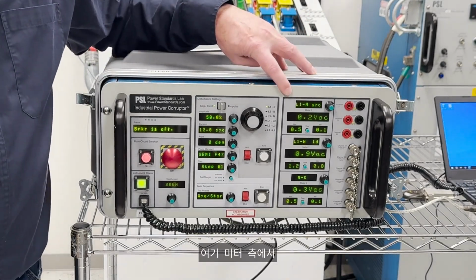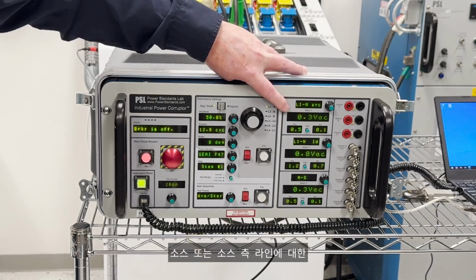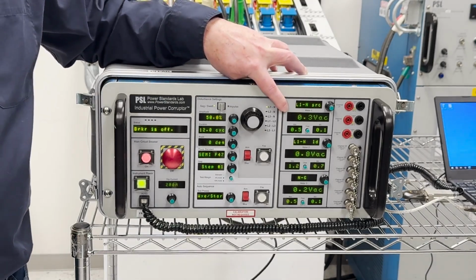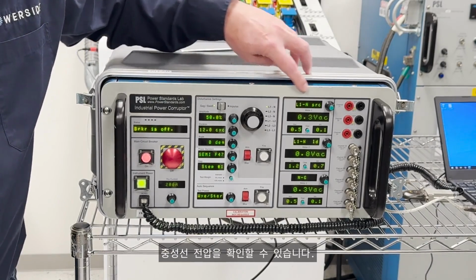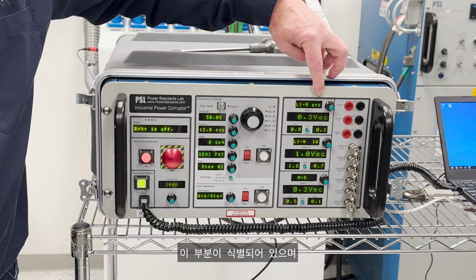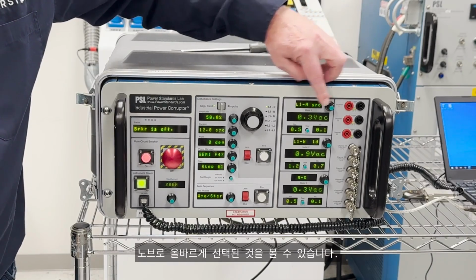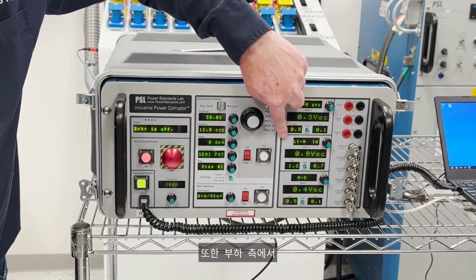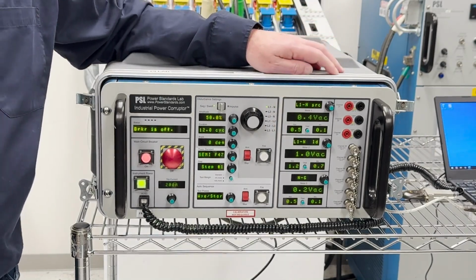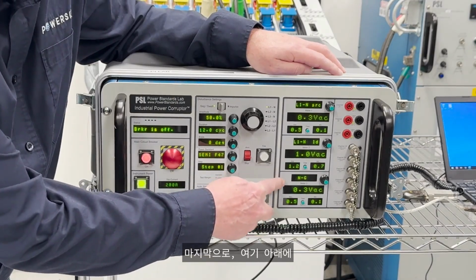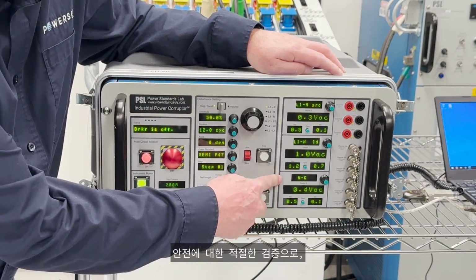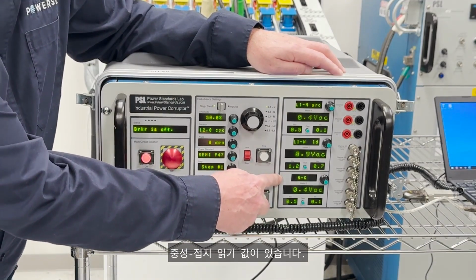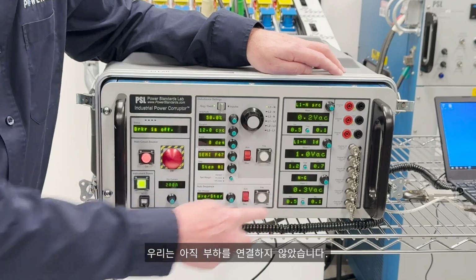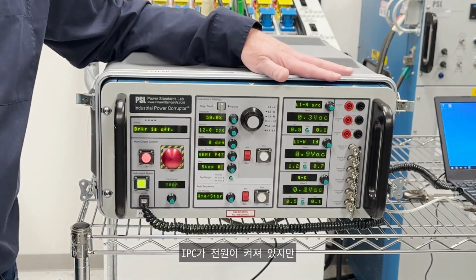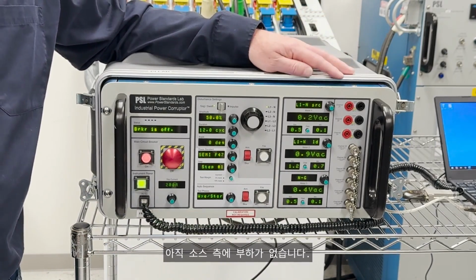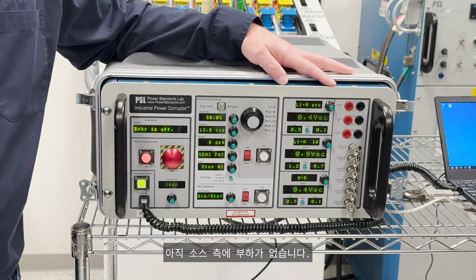We have here on the meter side the readings for the source, or the source side, line to neutral voltage for the source. You can see it's identified here and properly selected with the knob. And then we also have pulled up line to neutral on the load side. Finally, down here, as a proper validation on safety, we have a neutral to ground reading. And you can see here that we have not connected the load yet. The IPC is powered up, but we do not have load to the source side as yet.